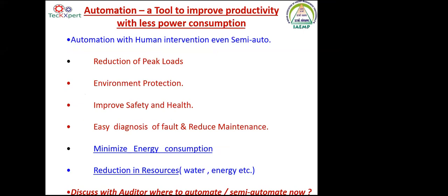Here, I should say, the essence and byproduct of automation for a given industry is energy conservation and energy efficiency. If you are able to automate many of your utilities or machines in your plant, the peak loads can be flattened, and the environment protection is also automated. We have basic automation. On your screw compressor, if you take the pressure control sensor from the main hood of the compressor and relocate it to the compressed air receiver, the zigzag pulsations, which operate from, say, 40 kilowatt to 120 kilowatt, will come within 60 to 70 kilowatt. The zigzag band definitely narrows down and gets stabilized.